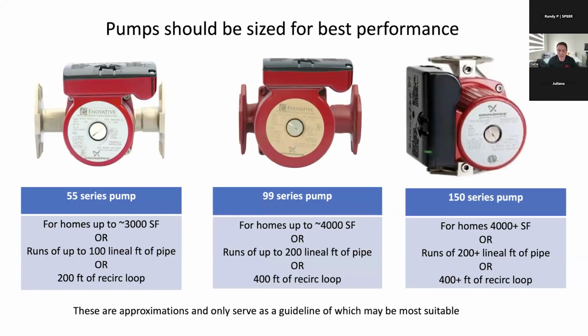It is recommended for residential that you size the pump. A lot of tankless water heaters have a built-in recirculation pump, and it's a very small recirculation pump. If you're operating that pump on demand and you have that tankless in a very large, 4,000 square foot house, it might time out. It might take longer than 5 minutes to prime that loop. So we always recommend that you size the pump based on the size of the house and the length of the plumbing run, so that when the pump is activated, you get the hot water in the quickest manner. Because the faster you're running the water through your line, the faster the pump is going to shut off.